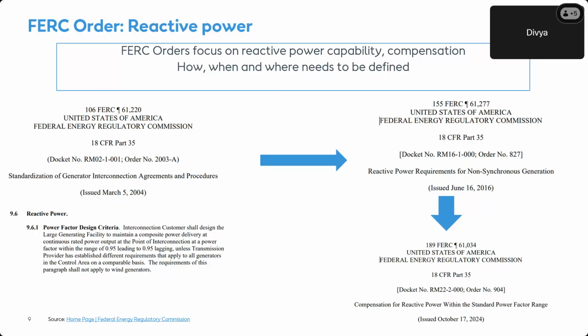It helps in designing upfront rather than fixing things later because the grid requires something. That's a fantastic first step. Also, recognizing that the technology exists today has pushed FERC to be firmer about that. Starting in 2016, it was mandated that every non-synchronous machine or plant must provide reactive power capability. The latest FERC Order 904 talks about compensation and getting rid of that compensation.